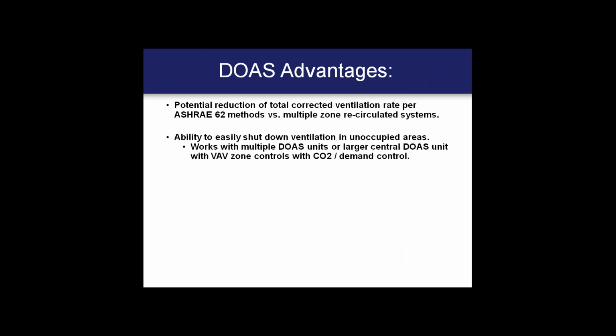Some of the advantages, though, I think are important to note when applying DOAS systems, because those are the most common application of fresh air with the VRF technology. I think number one is the potential reduction of total corrected ventilation rate per ASHRAE 62 methods. When you're dealing with centralized air handler type systems, you have to penalize and correct your total outdoor intake flow based on the worst case zone. So there's a penalty factor associated with that. By decoupling that fresh air and delivering it direct to each of those spaces, that allows you in many cases to reduce the total corrected outdoor intake.